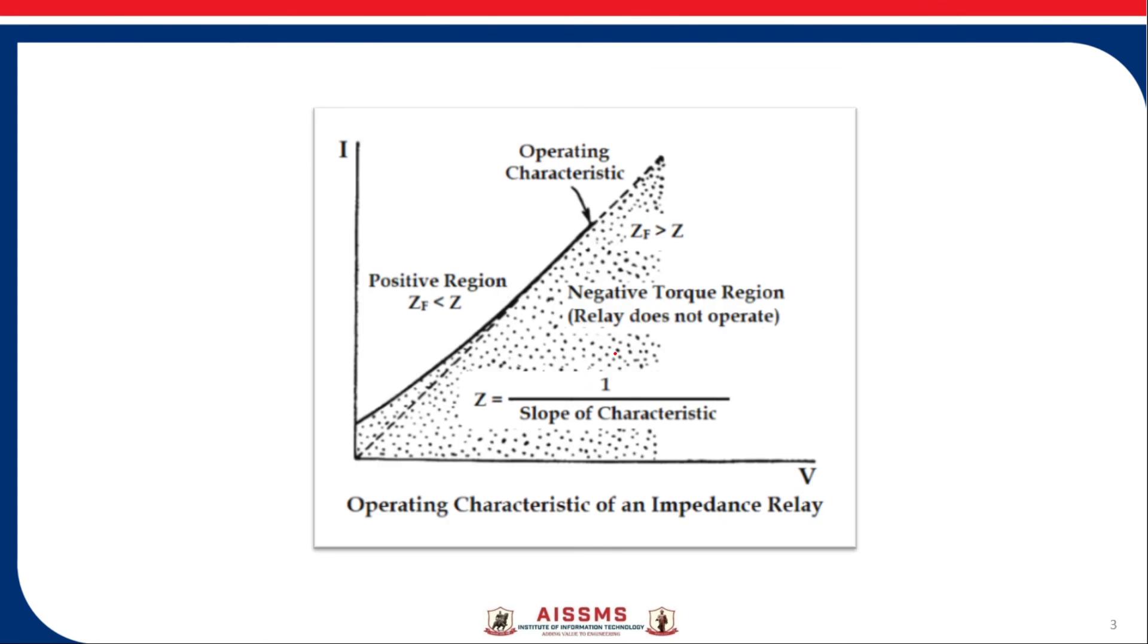The operating characteristic of an impedance relay: The impedance relay can sense the ratio between voltage and current at a point on a line. The impedance between location of CT PT and the fault is proportional to the distance between the CT PT location and the fault. Hence impedance relay is called as distance relay.